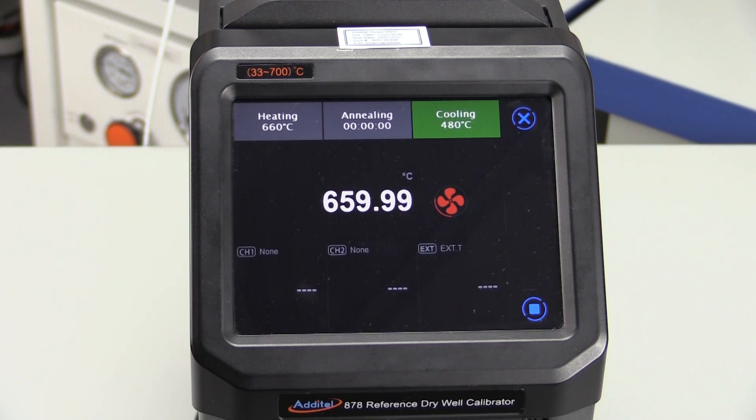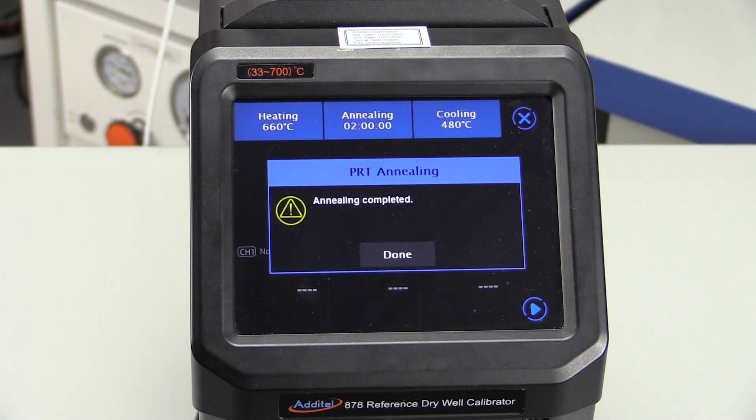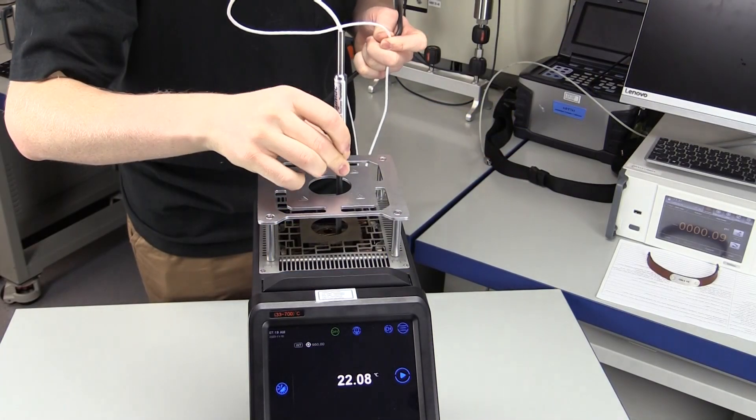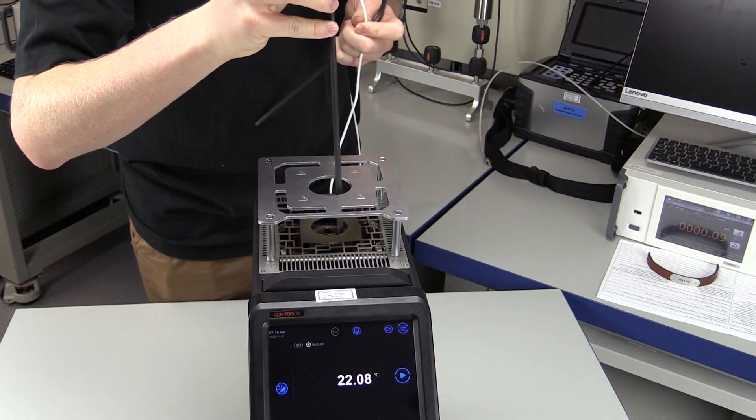Once the automated annealing process completes, the 878-700 will display a completion message. When the probes have cooled and it's safe to remove them, remember to handle them with great care as mechanical shock is a major contributor to changes in the sensing element.